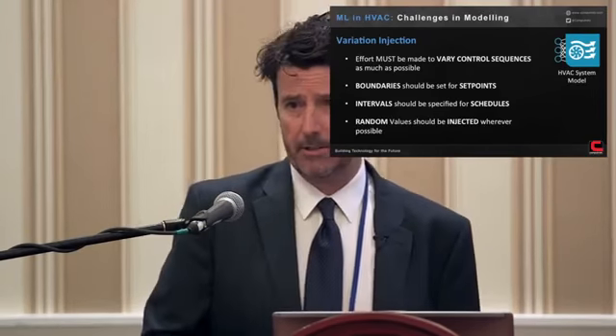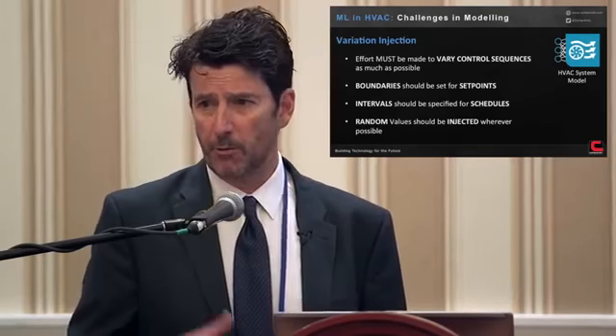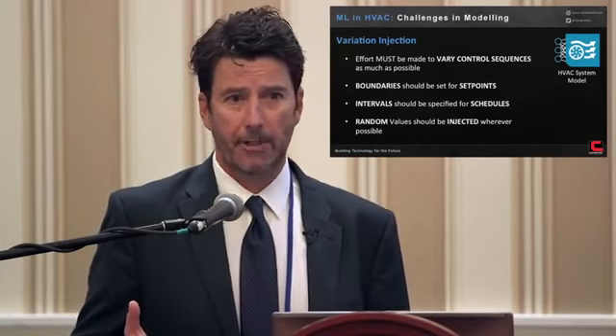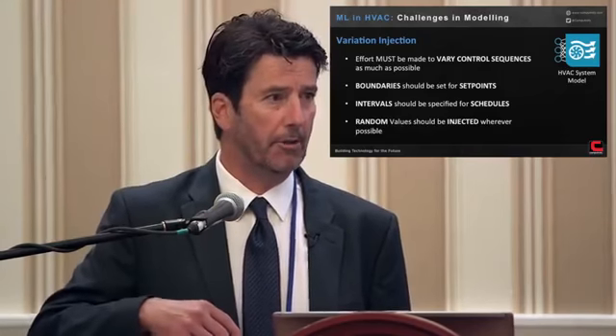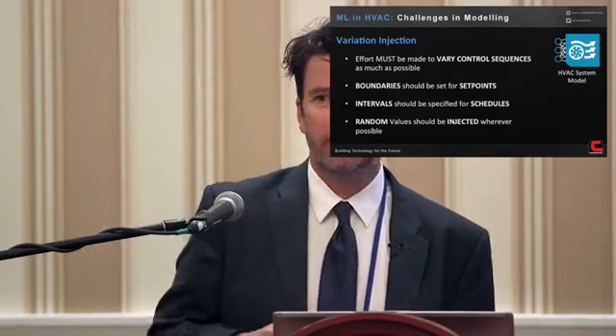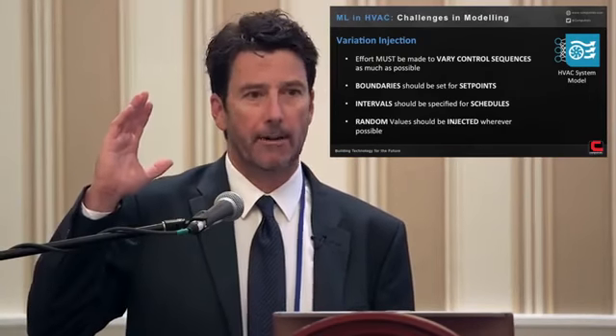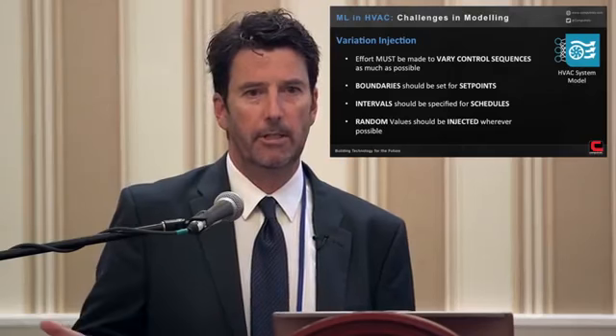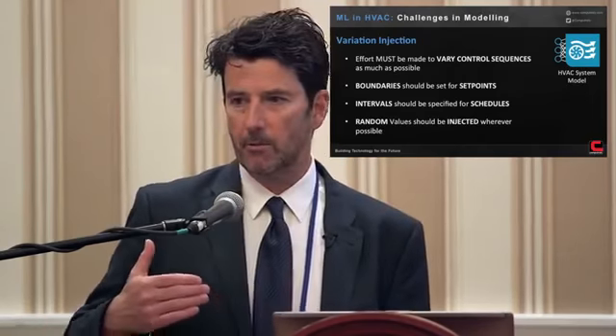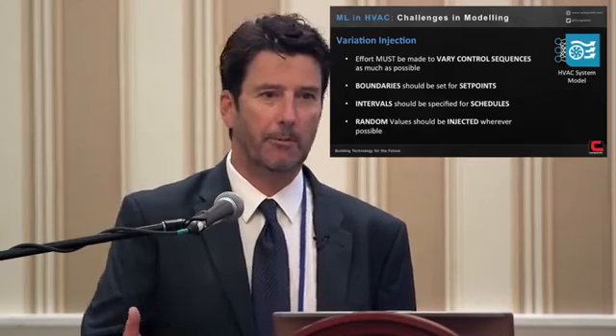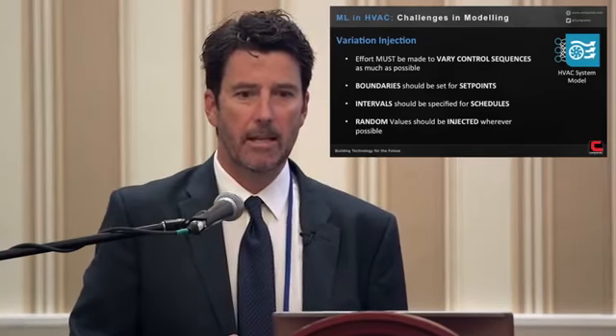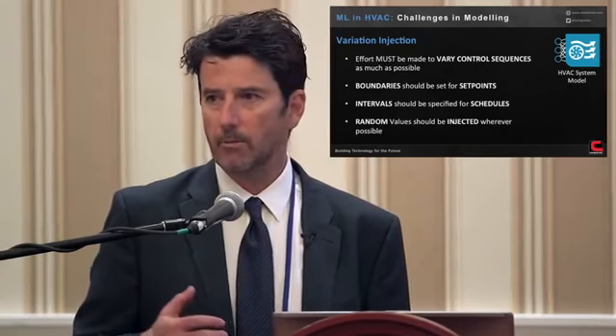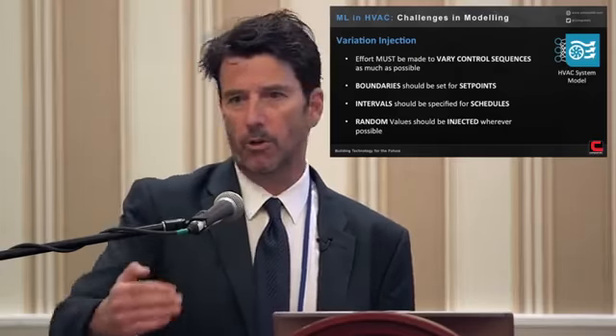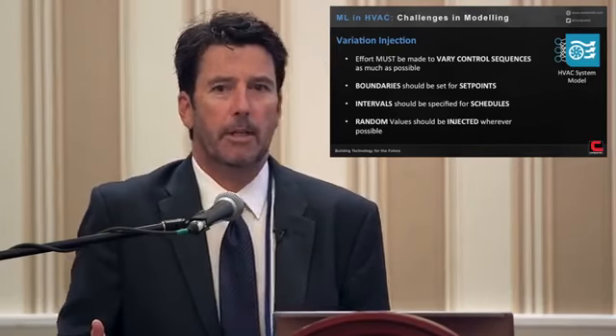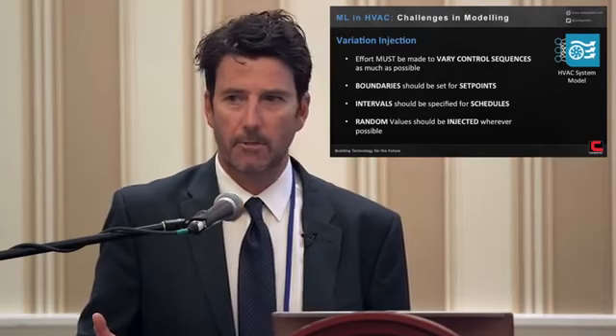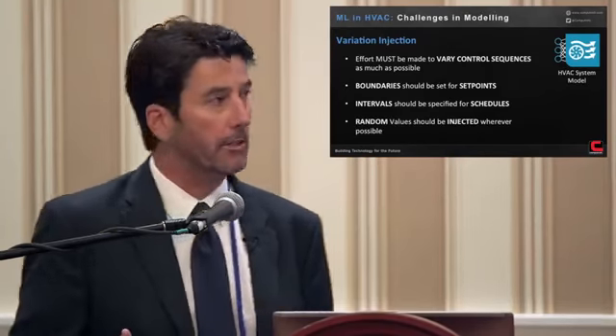One example of this is, some buildings require that you don't start all the air handlers at the same time. Big motors, you turn them on, there's an inrush current. Sometimes you might see a light dim if a motor goes on next door. You can't go into a building and just bang 100 air handlers at the same time. So we have a feature to do a delay start. Before doing this, we would just specify the sequence: we'd start one, then we'd start two, then we'd start three. Now, to do variation, we randomly sequence those. We'll start them in a different way every day because it's really unimportant to the building. We've already made the decision we're not going to start them at the same time. So that's a good opportunity to inject variation.